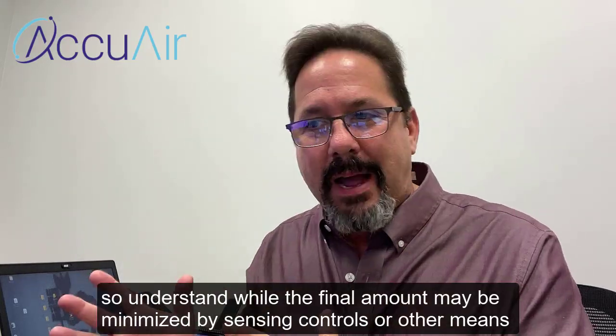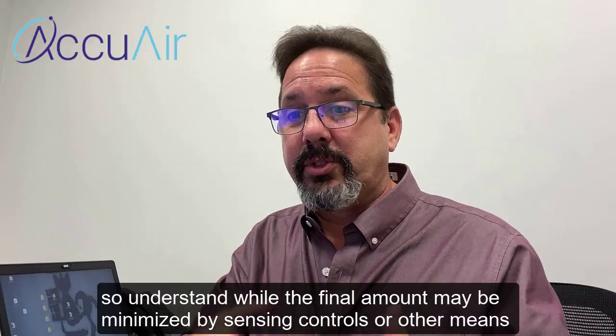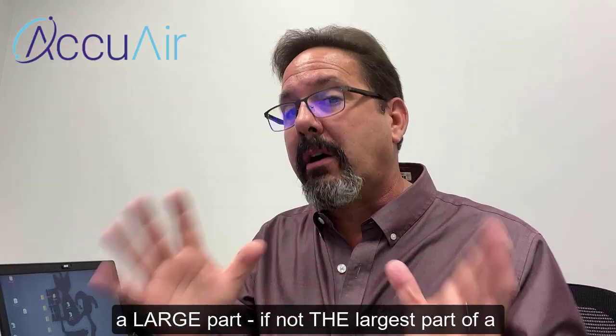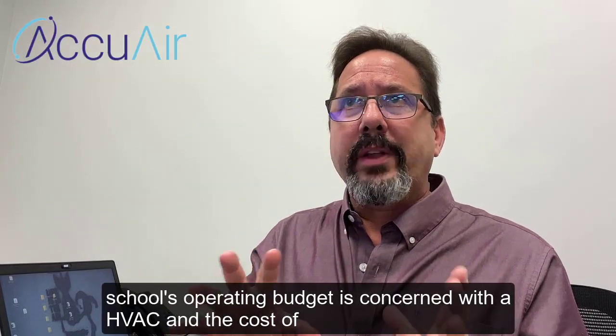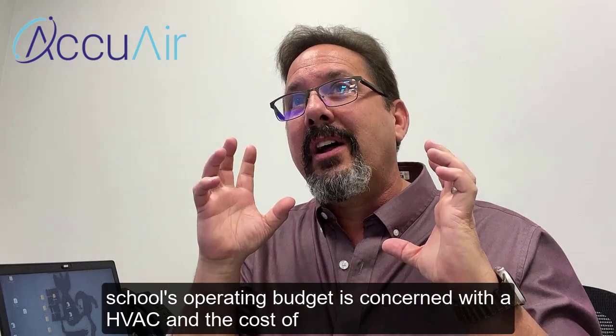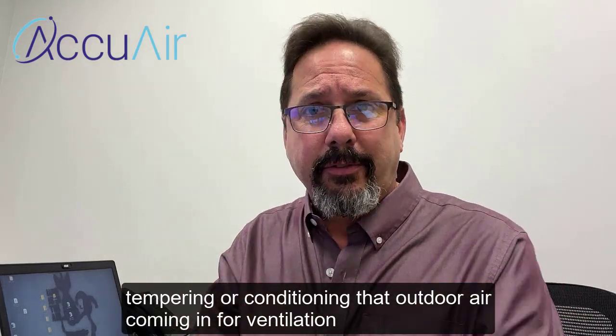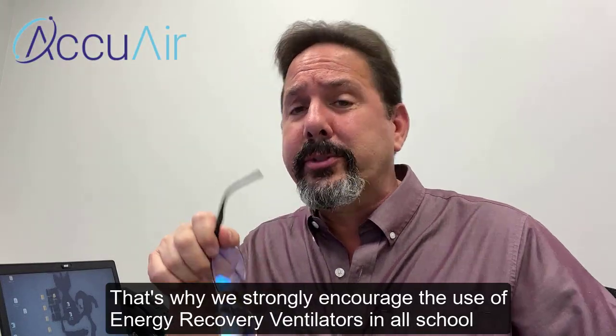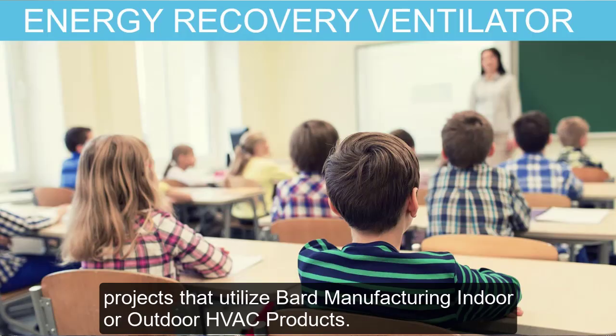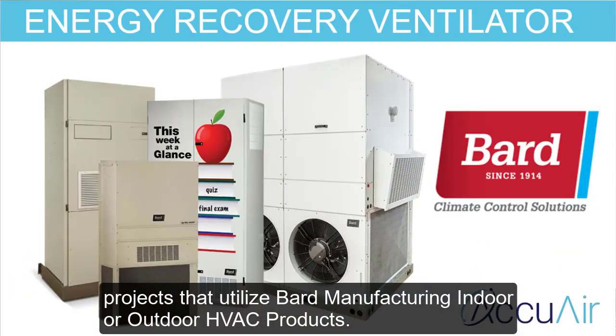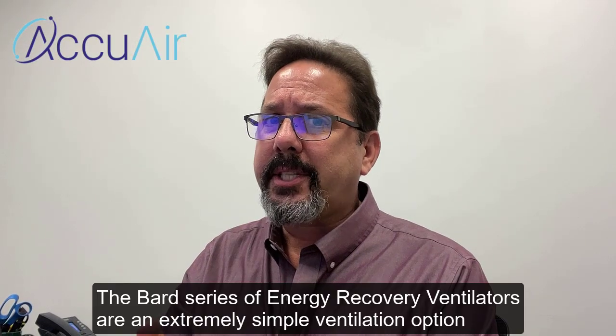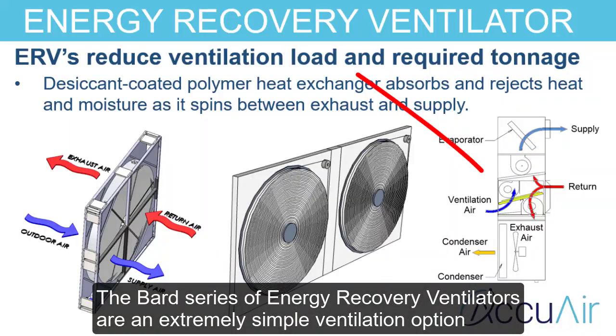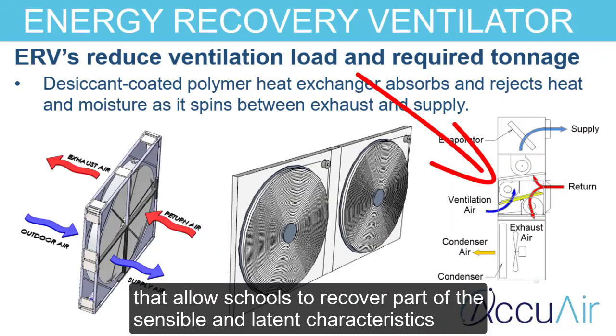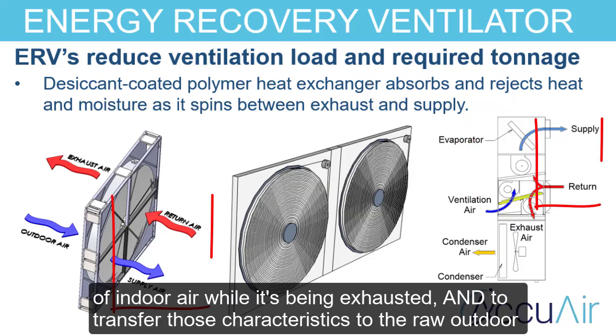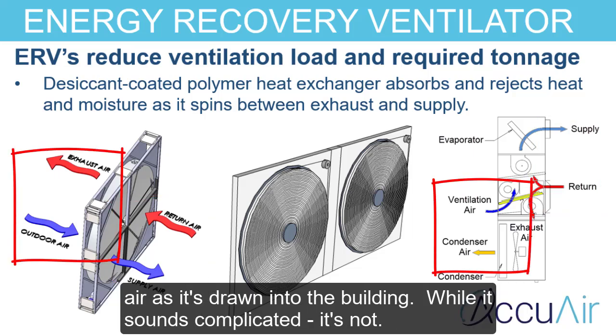So understand while the final amount may be minimized by sensing controls or other means, a large part, if not the largest part of a school's operating budget is concerned with HVAC and the cost of tempering or conditioning that outdoor air coming in for ventilation. And that's why we strongly encourage the use of energy recovery ventilators in all school projects that utilize Bard manufacturing indoor or outdoor HVAC products. The Bard series of energy recovery ventilators are an extremely simple ventilation option that allow the schools to recover part of the sensible and latent characteristics of the indoor air while it's being exhausted and to transfer those characteristics to the raw outdoor air as it's drawn into the building.